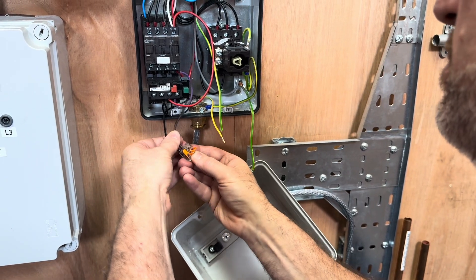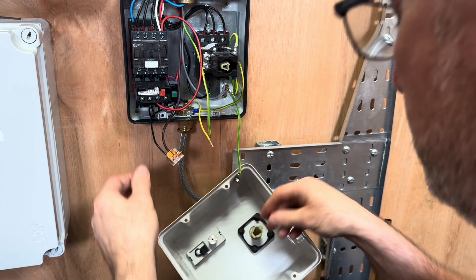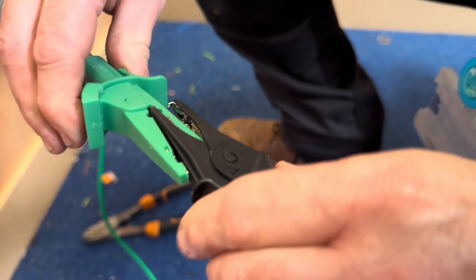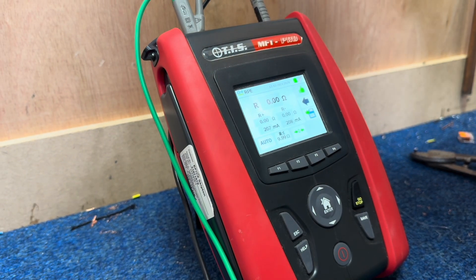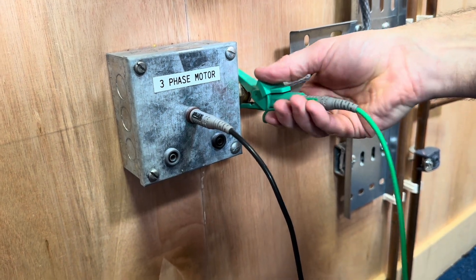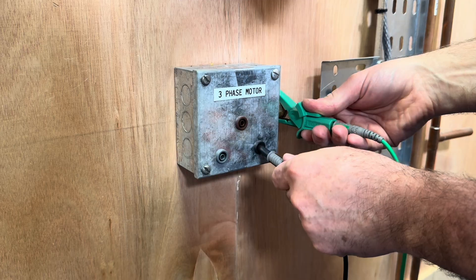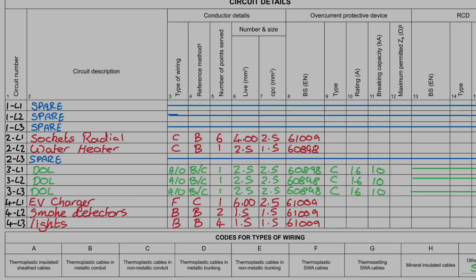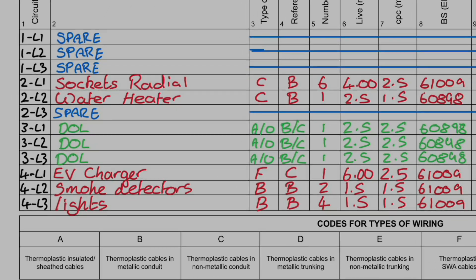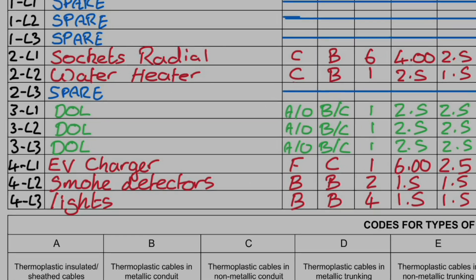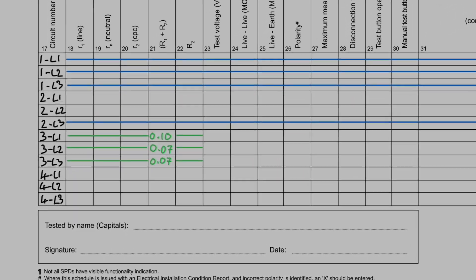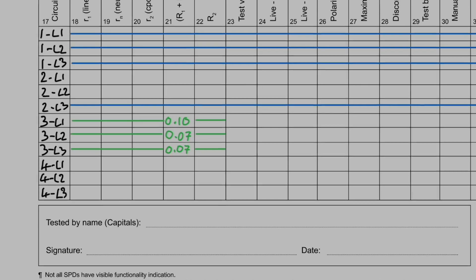With the line conductors linked out in the DOL and the leads of the MFT Pro nulled out, we can start the test. L1 is 0.1, L2 is 0.07, and L3 is 0.07. You need to record all three of these results on your schedule of test results, because the motor circuit is three-phase it should take up three rows. Many learners have taken only the highest reading and recorded it, which is not correct.